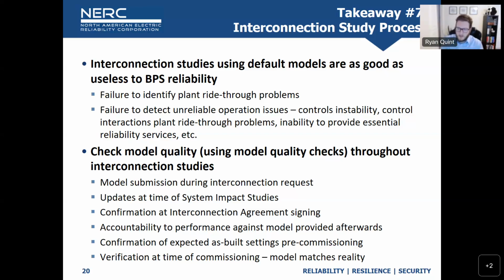Then why did you run the system impact study in the first place? Because you're using model parameters that don't actually show what the plant's going to do when interconnected, and that's a big problem right now. We have that across the board pretty heavily, given the current process we have, and we aren't truing up down the road to make sure that it matches what actually gets installed, and flagging it when it doesn't so someone can restudy it. Someone's got to make sure that when that plant closes the breaker, it's going to reliably operate through a fault, which is why we have all these big events.